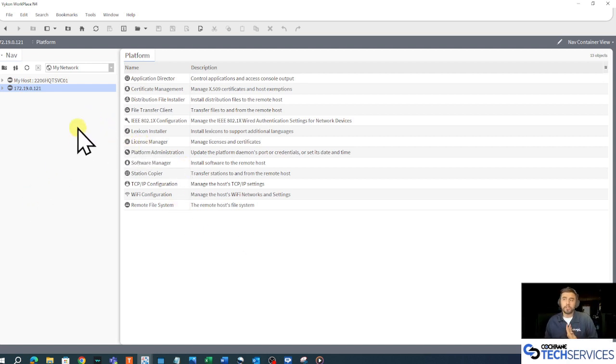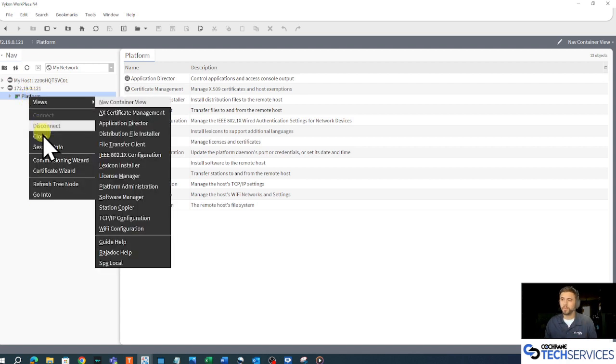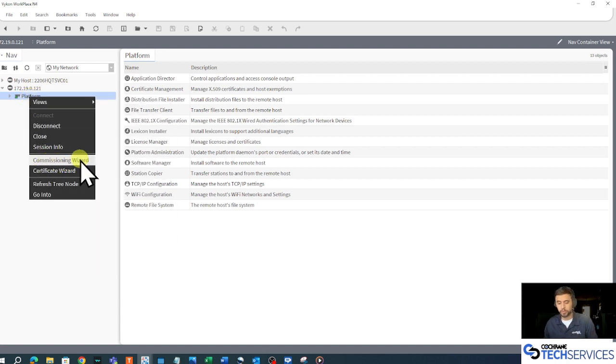So the way that I would do it is I would just expand that IP address of my JACE that I'm talking to and expose that platform. I can then right-click that platform and left-click this commissioning wizard.